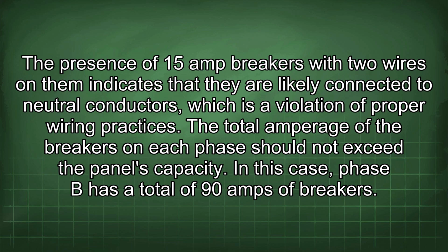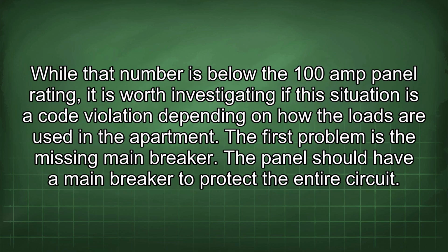The total amperage of the breakers on each phase should not exceed the panel's capacity. In this case, phase B has a total of 90 amps of breakers. While that number is below the 100 amp panel rating, it is worth investigating if this situation is a code violation depending on how the loads are used in the apartment.